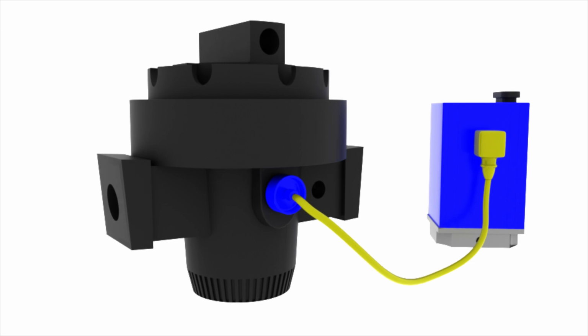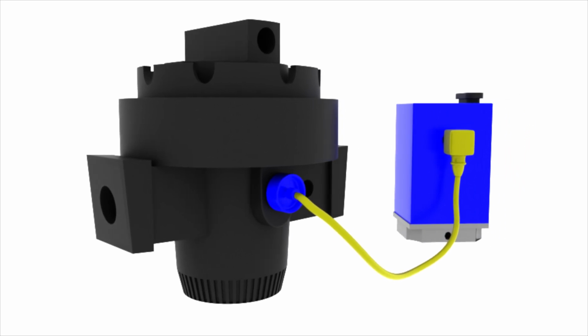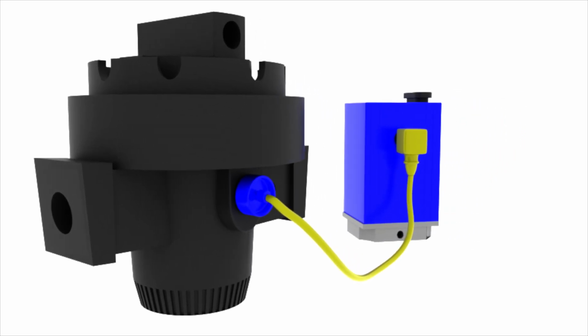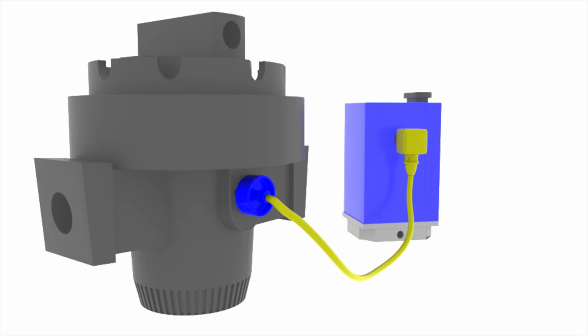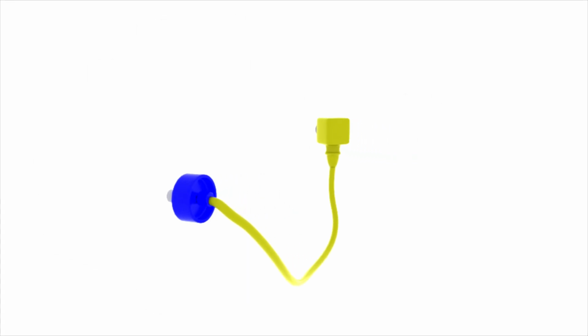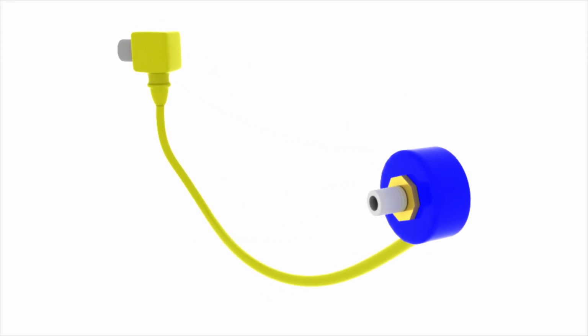A key role of transducers is to maintain consistent pressure levels in pneumatic systems. The QB2X supplies pilot pressure to a volume booster. A transducer is used to compensate for pressure and mechanical hysteresis losses across the volume booster.